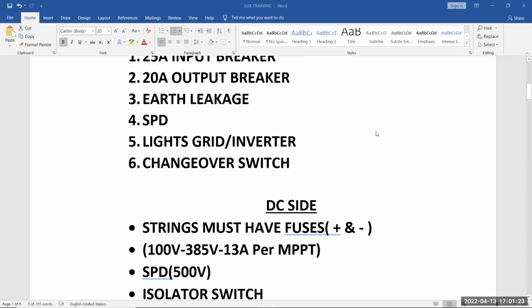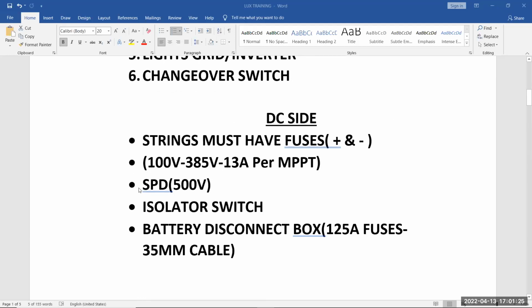Then on the DC side, I see you have a question there for the DC breaker. Yes, you can use a DC breaker instead of a fuse. The only thing with DC breakers is the more a DC breaker trips, the less resistance it has to the amps. So at the beginning, it will trip, let's say, at 16 amps. If you trip it again and again, it will become lower and lower, and you start tripping at 15, 14, 13, 12, and so forth. But yes, you can use a DC circuit breaker in place of fuses.